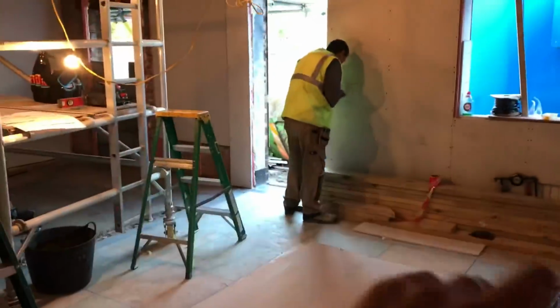Right, and it's cutting some boxes out now. We've gone round and marked up pretty much where they want sockets and power and stuff, so we're going to go around, cut all these out just with fast fix boxes. We've got a ring main in this area, a ring main in the front, 2 lighting circuits, smoke detectors and stuff, so let's crack on. So just so you know, all of our sockets are going at 450 to the bottom, and all the switches are 1200 to the top.